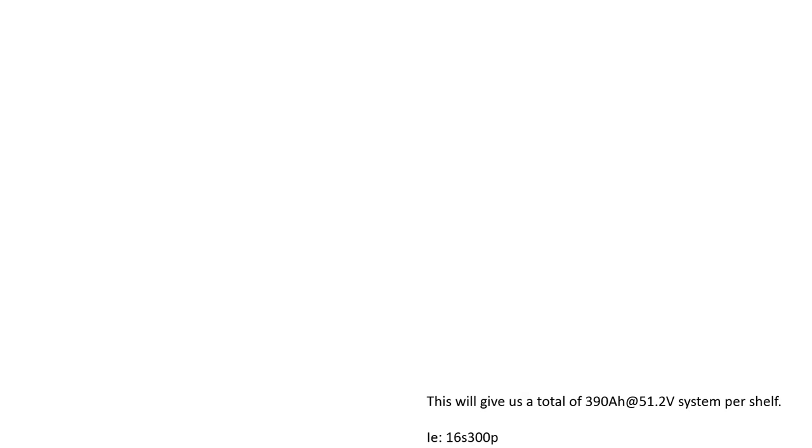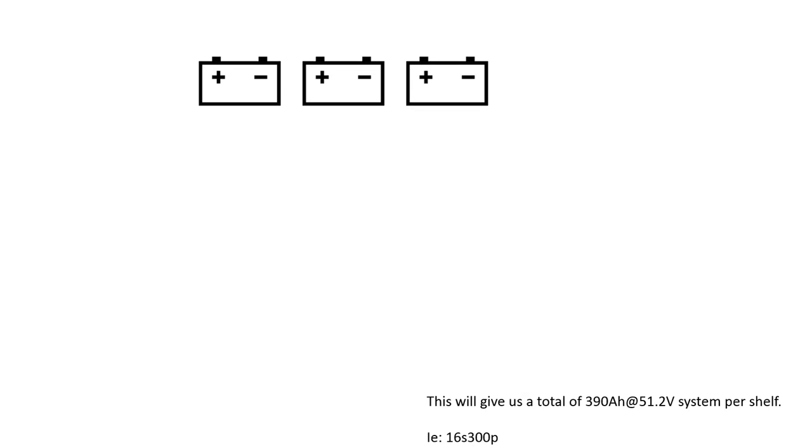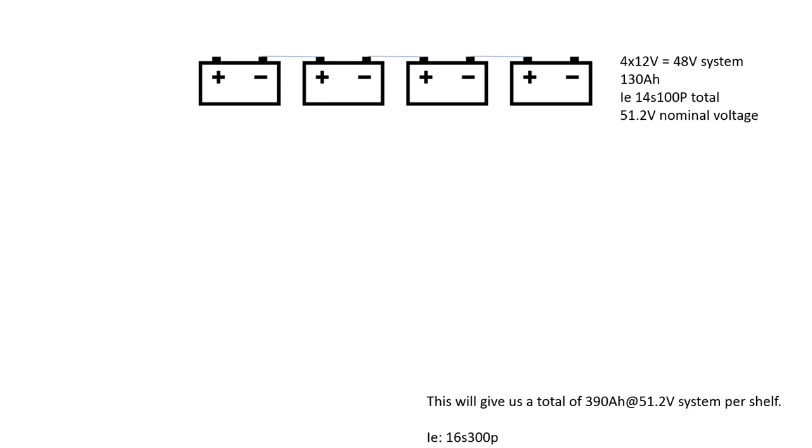It's now time to actually look into and see how it all conforms together. First shelf, this is containing four batteries in series, those four hooked up with the same equal length of wires. Then I parallel that battery bank, then conform up to a four times 12 volt system and that equals 48 volts. We have roughly 130 amp hours now and a total of 14s 100p system.